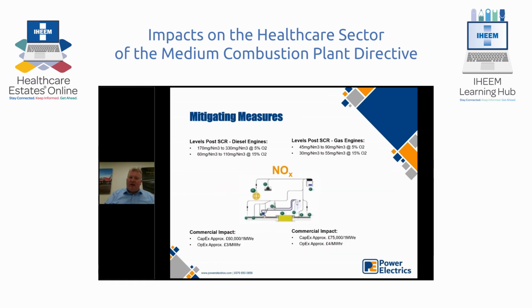So just a little bit of an idea on these mitigative measures, what it equates to, how much it is going to cost you, and what the impact is for everybody here. By putting an SCR system on, you can drop that down to 60 to 110 milligrams, up to a 95% reduction. Similar to gas, you can get it down to well below 50 by using SCRs and these mitigating measures, but that comes at a cost.